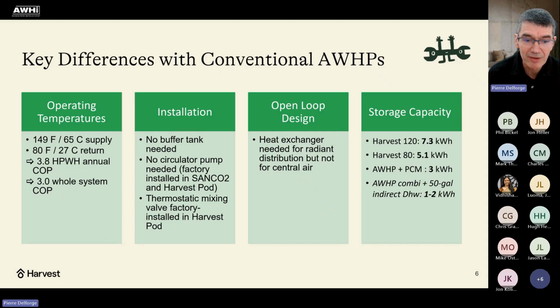It is an open loop design, meaning that we don't need a heat exchanger on the distribution side, except if you do radiant or other non-potable distributors. But for forced air, we have an NSF 61 rated coil, and we have circulation controls to make sure the water never stagnates in the distribution system, and that avoids the need for a heat exchanger, which increases efficiency.